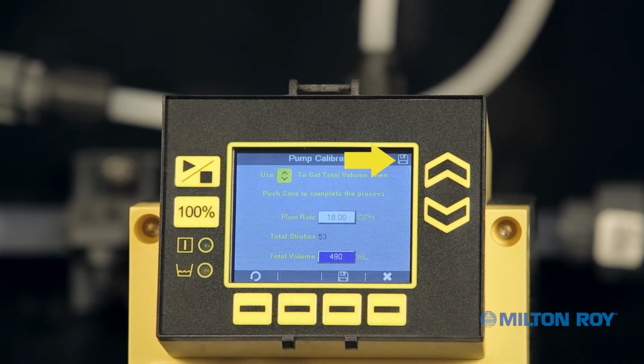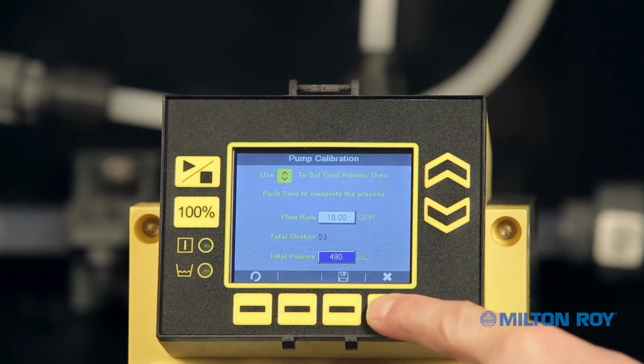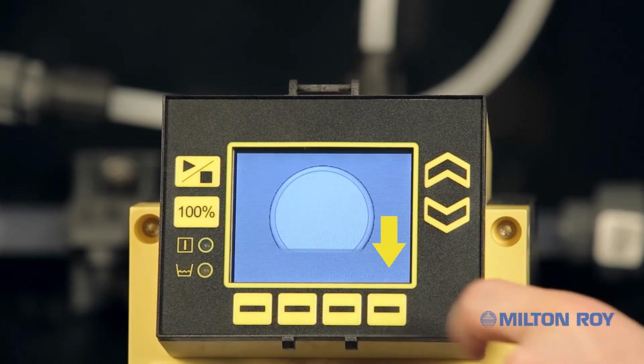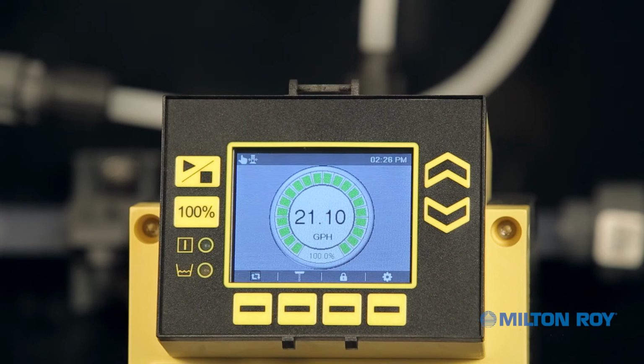Notice the small save icon that appears briefly in the upper right corner of the screen. Calibration is now complete. To exit the calibration screen, press the context-sensitive menu button Exit twice. Once back at the main display, the screen will reflect our calibration changes. A calibration icon is displayed in the upper left corner of the notification area, indicating that the pump is now calibrated.